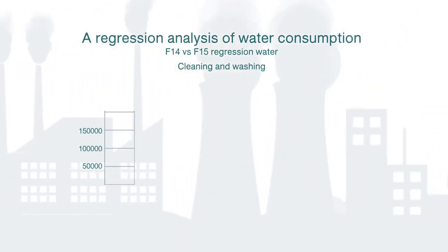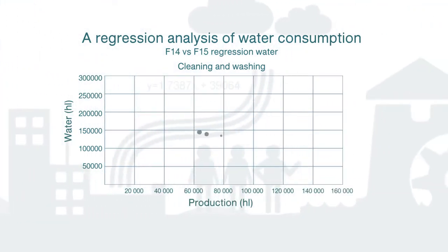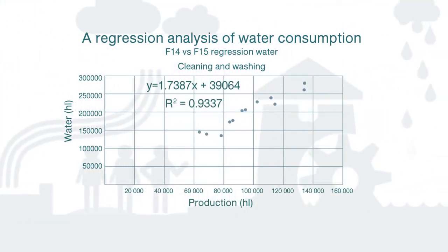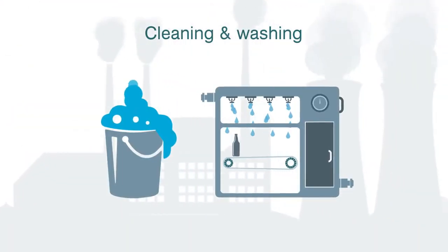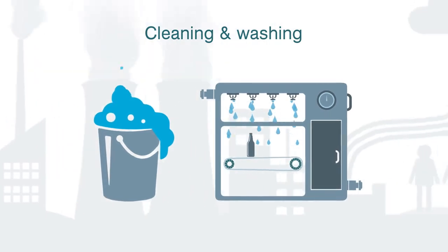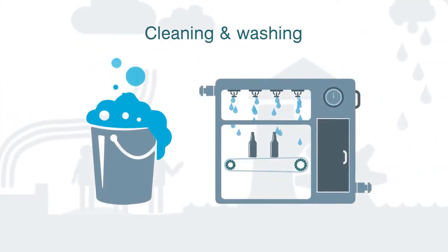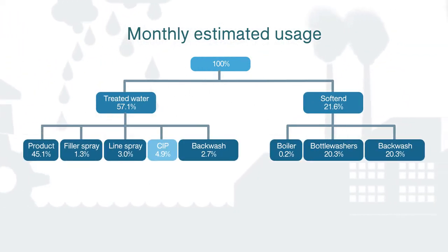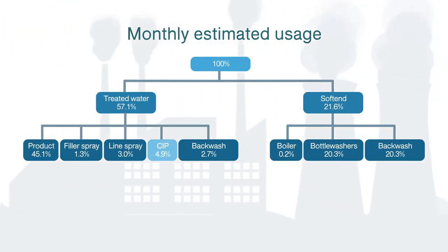The data was plotted using regression analysis to determine the water baseload and baseline for the production site. The results highlighted cleaning and washing within the process as a significant contributor to water consumption. A common practice opportunity was identified to recover and reuse the final rinse water from the cleaning-in-place (CIP) operations.